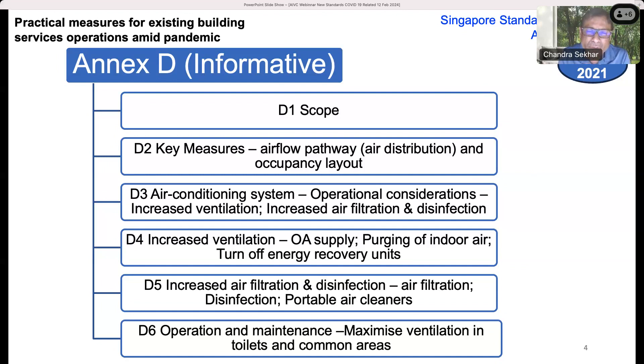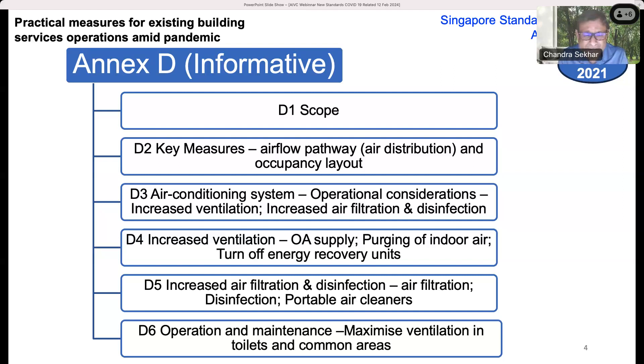We talked about air distribution pathways, airflow pathways, and occupancy layout. In terms of operational considerations of the air conditioning system, we said we have to increase the ventilation, increase air filtration and disinfection where possible. For increased ventilation, we increased outdoor air supply, purging of indoor air, and turning off energy recovery — strategies that were discussed in previous presentations as well. The operation and maintenance part focused on maximizing ventilation in toilets and common areas to ensure good circulation and ventilation throughout buildings.